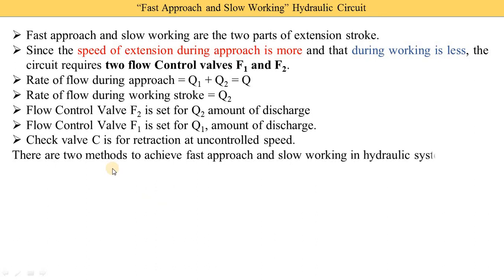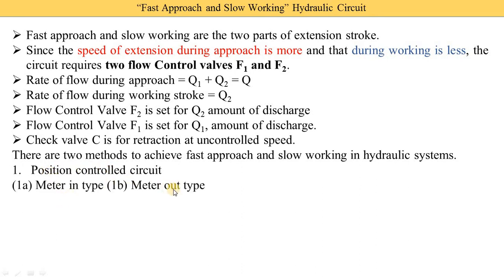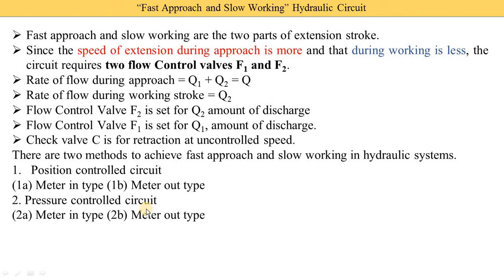There are two methods to achieve fast approach and slow working in hydraulic systems. The first is the position control circuit, which is again of two types: meter-in and meter-out. Position control uses a deceleration valve with a 2/2 directional control valve. The second method is the pressure control circuit, which uses a sequence valve, also available in meter-in and meter-out types. In this video, the position control meter-in and meter-out types are explained; a separate video covers the pressure control circuit.